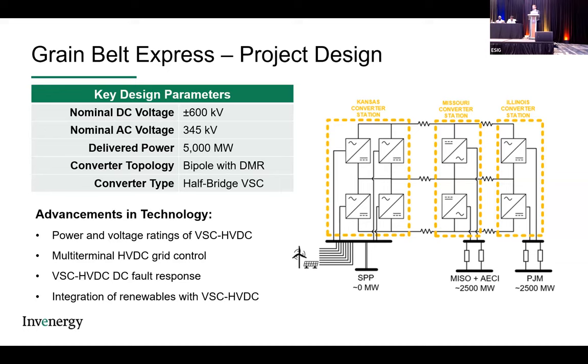It does have bipole with dedicated metallic return, and it's using the half bridge VSC. So there's, I think, a few key advancements that are coming with this project. Number one, something that jumps out is the power and the voltage ratings of the VSC. So 600 kV, and then thinking about an overall 5 gigawatt system, even if it's two 2,500 megawatt converters, that's still a step in technology that needs to be made here.